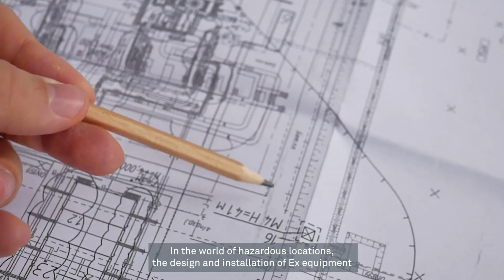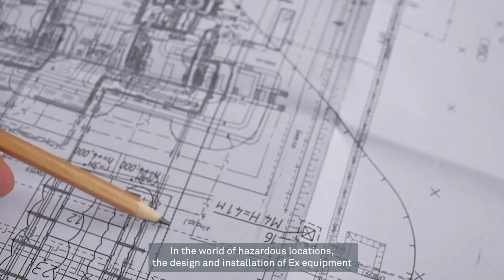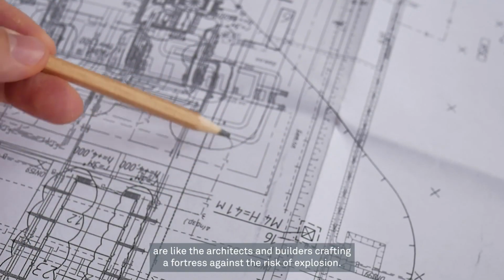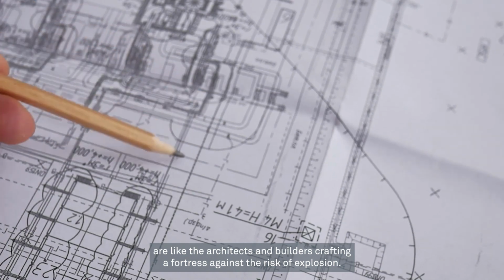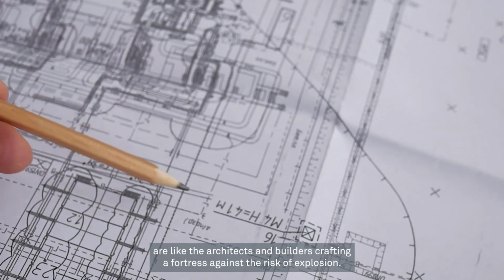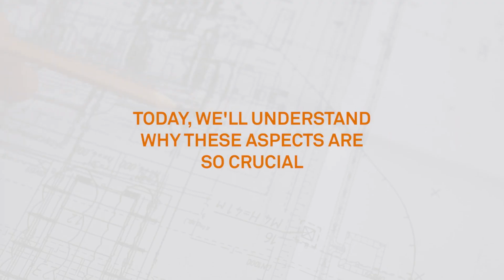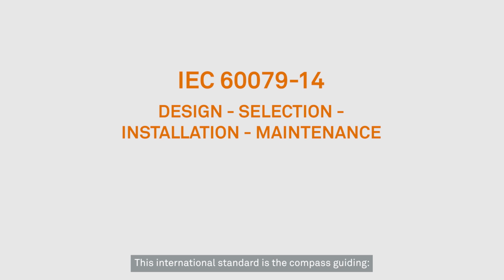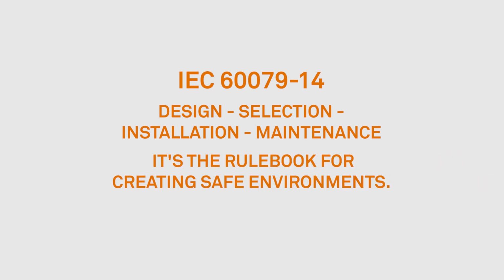In the world of hazardous locations, the design and installation of EX equipment are like the architects and builders crafting a fortress against the risk of an explosion. Today we'll understand why these aspects are so crucial. Enter the IEC 60079-14 standard. This international standard is the compass guiding the design, selection, installation, and maintenance of electrical installations in explosive atmospheres. It's the rule book for creating safe environments.